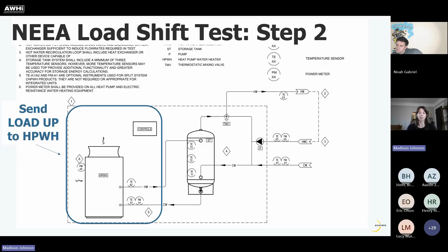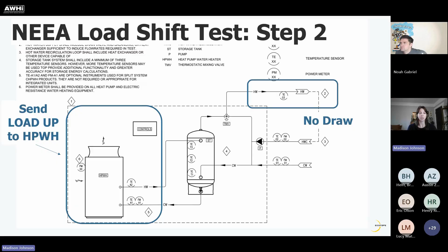Then moving into step 2, after the system is off in normal operation, we send a load up signal to the heat pump water heater and allow the tank to charge fully. So we're not actually sending a particular schedule or shed duration. We just want to see what the tank is going to look like when it's fully charged. So we'll wait for that heat pump to turn off during load up. This one's also done in 0 draw conditions.